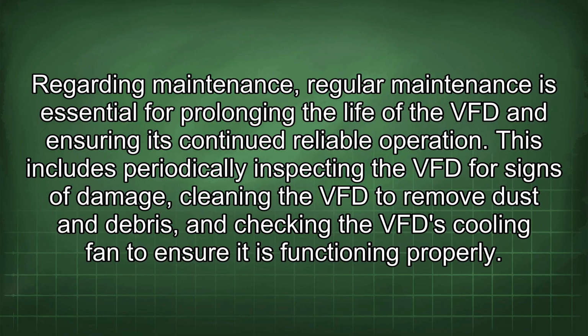Regarding maintenance, regular maintenance is essential for prolonging the life of the VFD and ensuring its continued reliable operation. This includes periodically inspecting the VFD for signs of damage, cleaning the VFD to remove dust and debris, and checking the VFD cooling fan to ensure it is functioning properly.